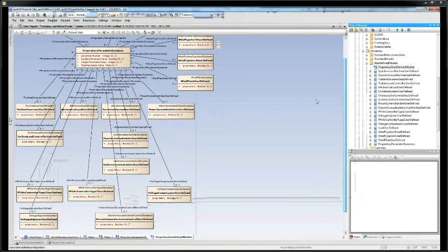So this is the proprietary dynamics, the support for how one can pass a generic mechanism that can be used for passing multiple parameters that are part of any type of particular dynamic component, so that you can define a dynamic component like an excitation system and then put as many parameters on that, not defined publicly anywhere, but you're saying parameter 1, parameter 2, parameter 3, parameter 4, and if both the sender and the receiver agree on what that ordering of parameters is, you could pass the information related to a given type of component.